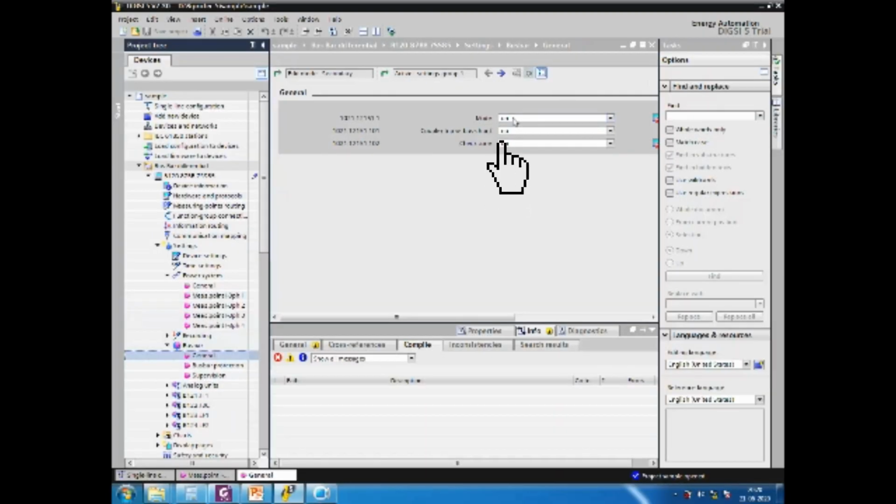Here in the configuration we made bus coupler tripping no. We are giving the option; previously I have mentioned it in the relay settings. Otherwise it will give the tripping to all. We have to configure tripping to both incomer and outgoing, so the full plant goes for shutdown.